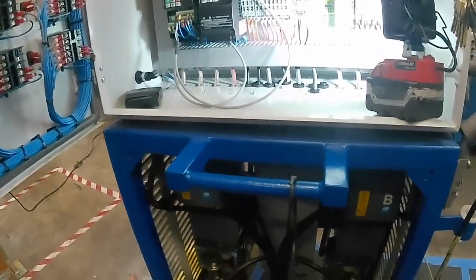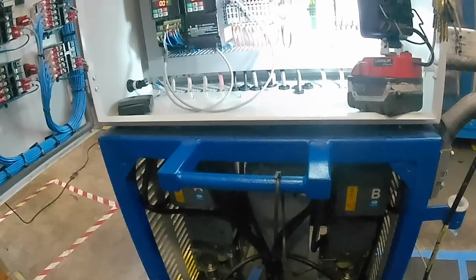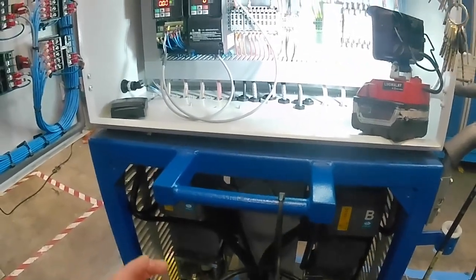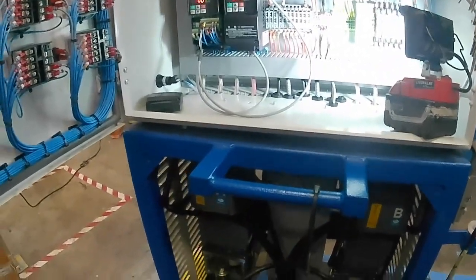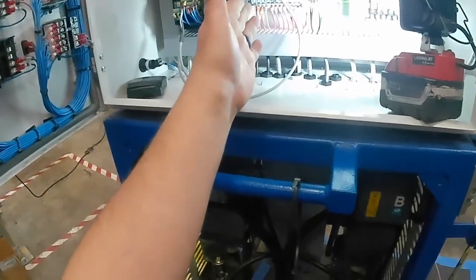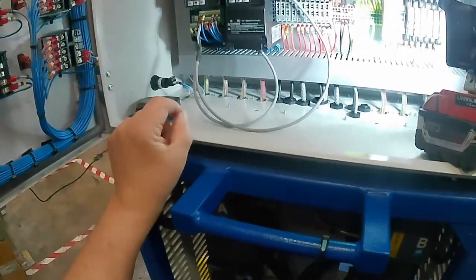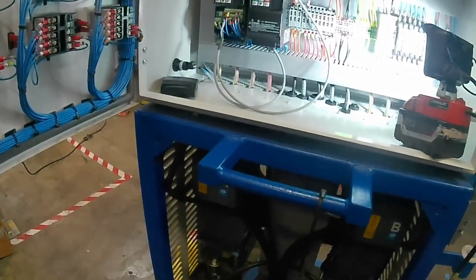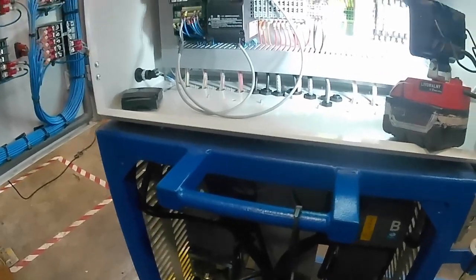We're gonna let this thing come up to temp before we turn it over to the operators and have them test it out, to see if it's gonna blow that fuse again. But if it blows, that's on the supply side of the drive, not the load side. I'm interested to see what happens here.